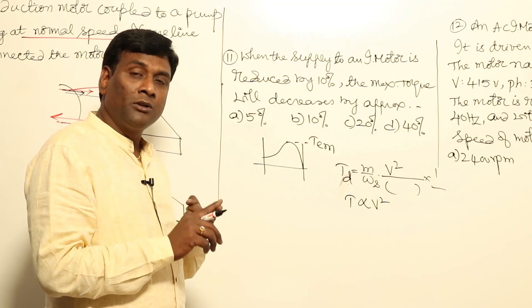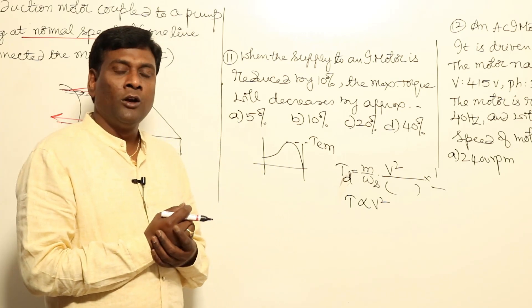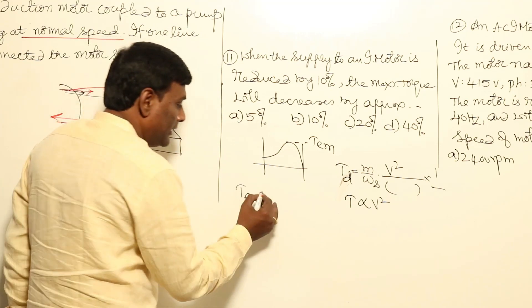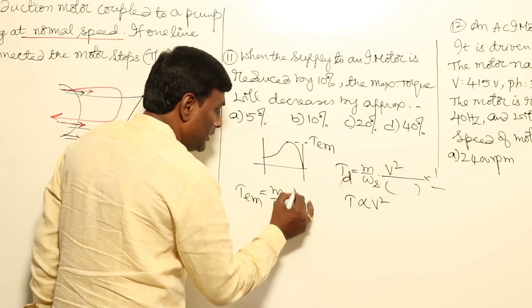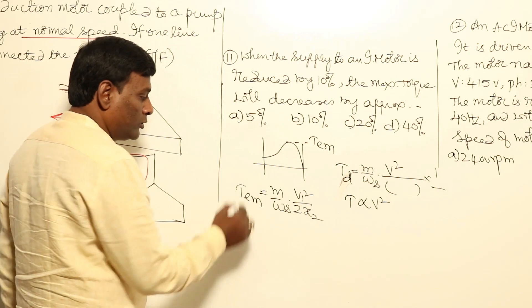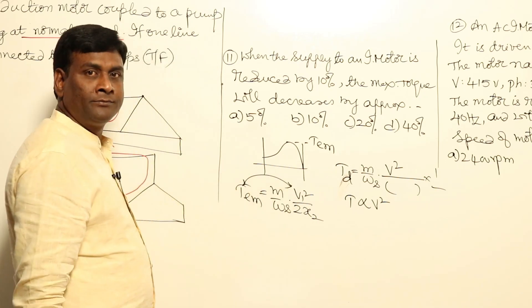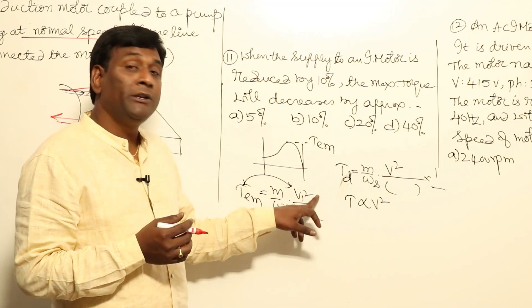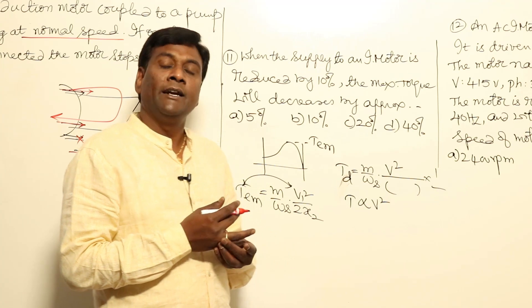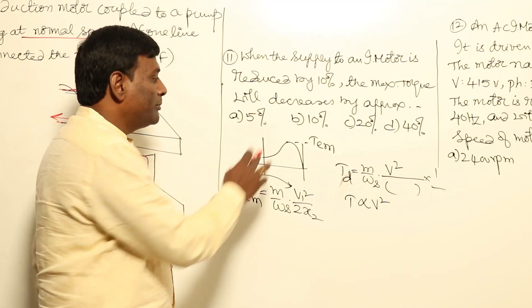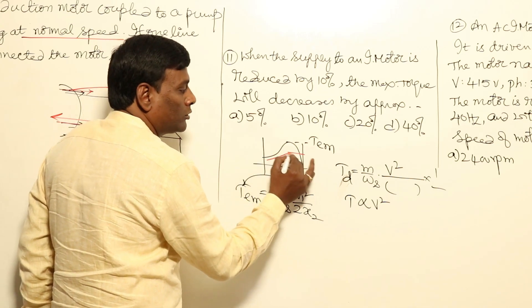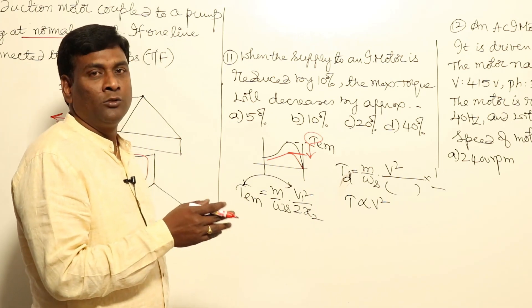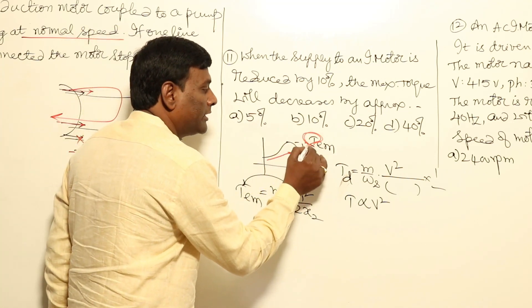The pull-out (maximum) torque Tm = (m / ωs) × V1² / (2X2), so pull-out torque is directly proportional to voltage squared. If I reduce voltage by 10 percent, the supply voltage becomes 90 percent. Then the pull-out torque becomes (0.9)² = 81 percent of the original. So the reduction is 100% − 81% = 19 percent. The pull-out torque will be reduced by 19 percent.